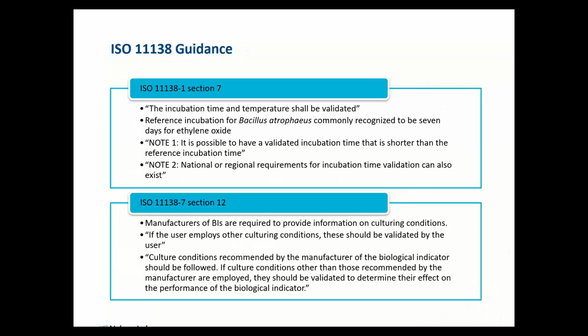I also wanted to take a moment to acknowledge the guidance that's given in ISO 11138. So in section 7 of 11138-1, it states that the incubation time and temperature shall be validated. So it's important to pay attention to the use of the word shall. That means that it is a requirement, not a recommendation. So these chapters are specific to biological indicators, and it is required to validate that time and temperature parameter.